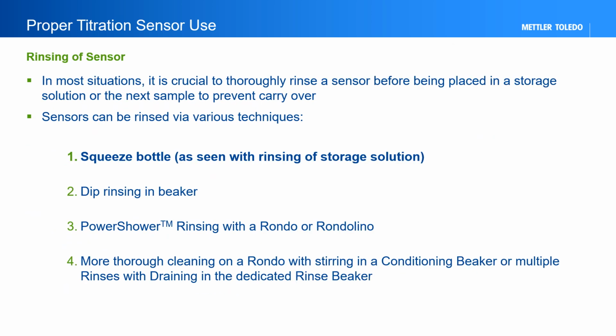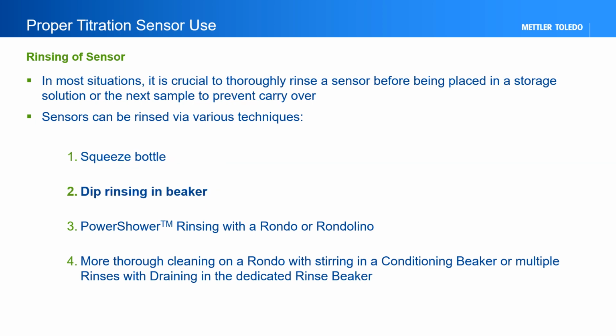After a titration or measurement, it is also necessary to remove the sample from the sensor before placing it back in the storage solution to avoid contamination. As seen in the previous video, removing the storage solution from the sensor, a squeeze bottle and rinse beaker can also be used to remove the sample solution before the sensor is placed into storage. Another option for rinsing is to use a dip rinse effect with a reserve titration beaker.